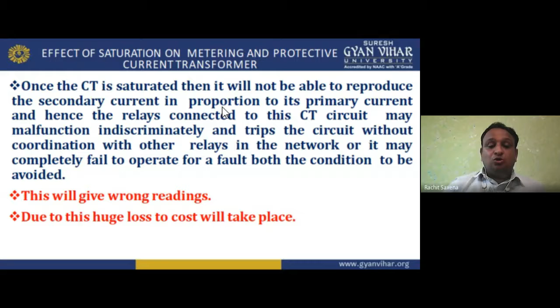I hope you understand. Now the remedies. What are the remedies we have? How can we do it? It is the duty of the protection design engineer. If you and I become protection design engineers, we have to do CT sizing. We have to do a current transformer sizing calculation so that the CT will not saturate for the worst case. We can make a CT design or sizing in this manner so that the CT will not saturate for the worst case through fault.